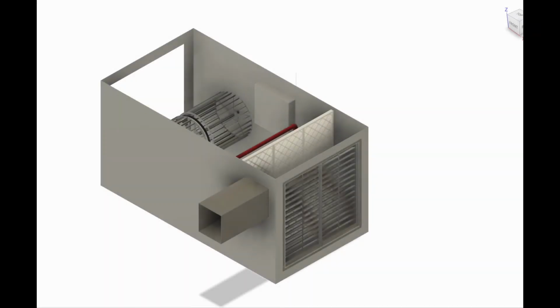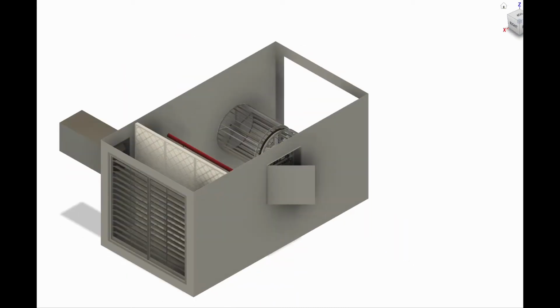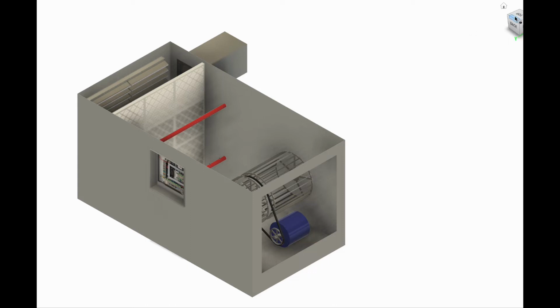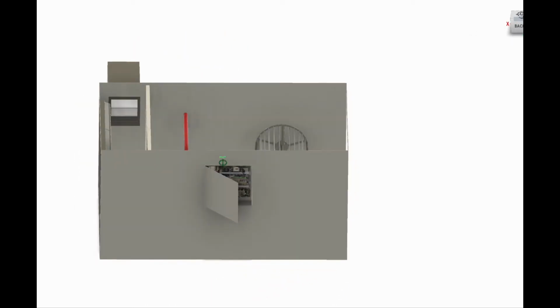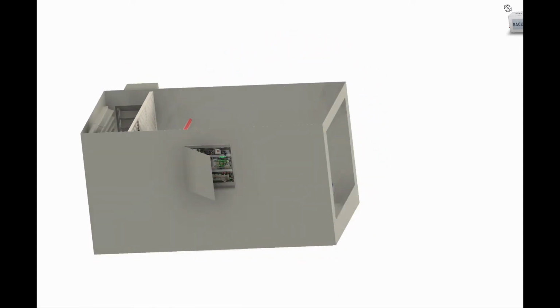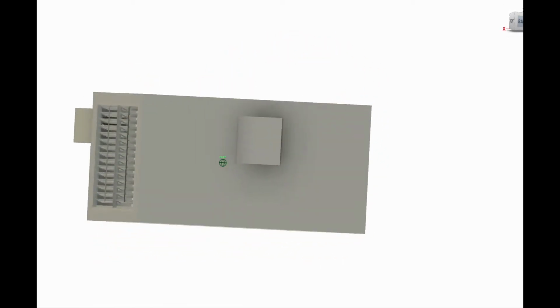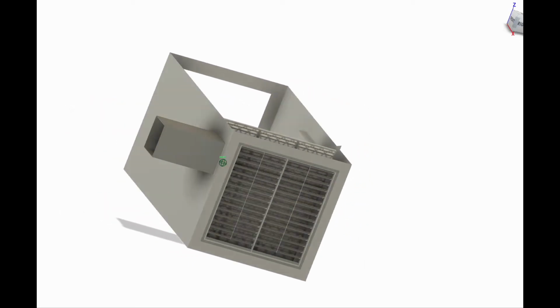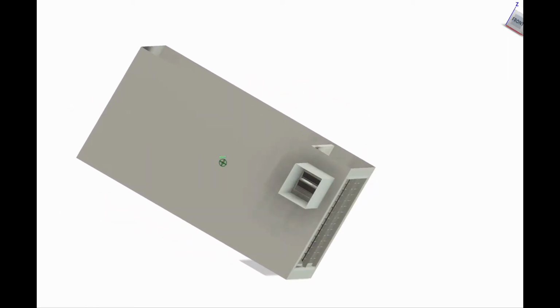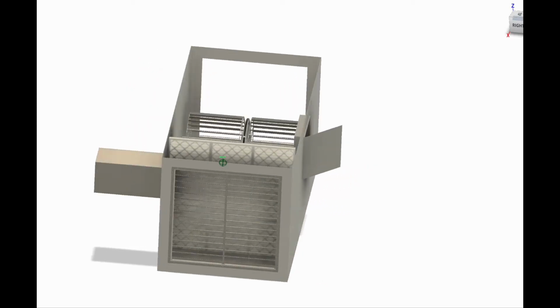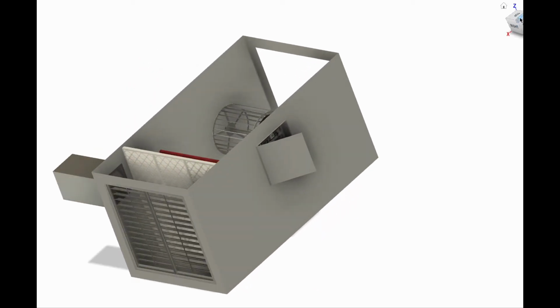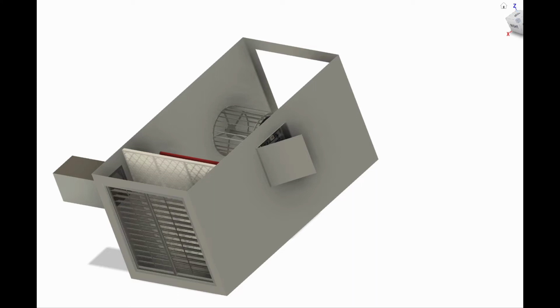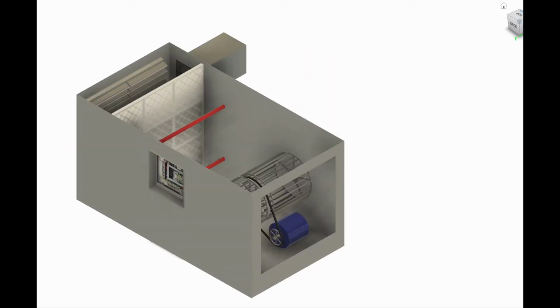So here's a mixed air type air handling unit. You can see you have your fresh air intake, but you also have a return coming back from the building. And there'll be a damper in there that controls that ratio of how much fresh air mixes with the return air. And here's your control panel. And again, that air will go through your filters before going back into the building. So I hope that makes sense, the difference between a pass-through air handling unit and a mixed or mixing air type air handling unit.